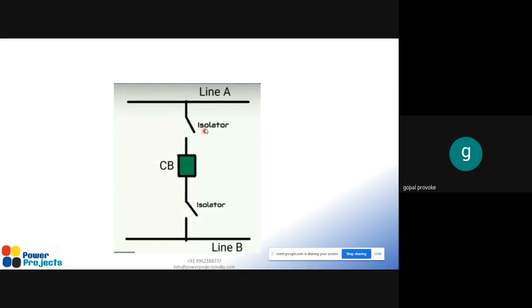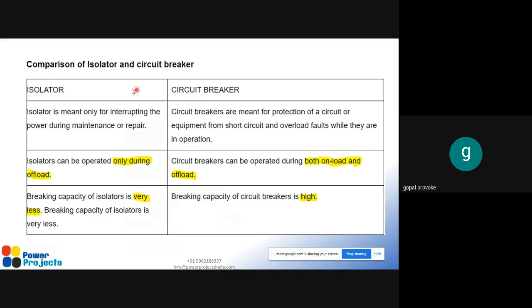What we will do is, first we will close the isolators. We will close the isolator of line A, second we will close the isolator of line B, and at last we will close the circuit breaker. So we will see why we are closing the circuit breaker last. This is the comparison between isolator and circuit breaker.